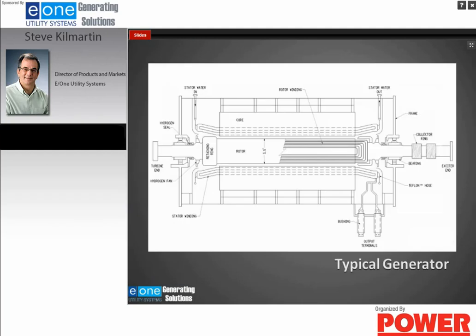This is a sectioned view of a hydrogen-cooled generator. I'll point out some of the important features. Why I am showing this is because we need to keep the hydrogen inside the generator. So all of the coils, all the electrical components are housed inside an iron case. Also, where you run into issues or problems is where the rotor, the rotating part of the generator, penetrates the generator, where it comes in and out of the generator.